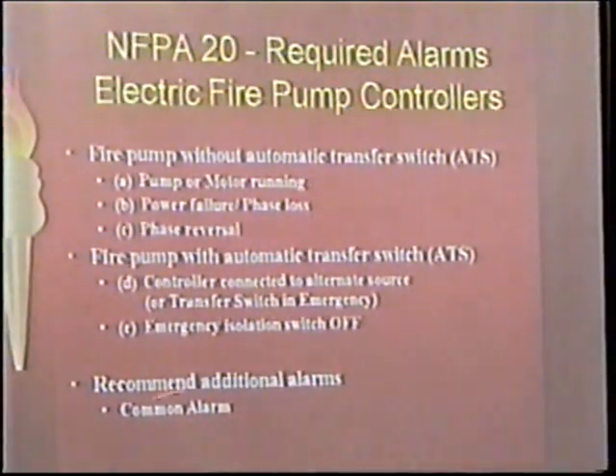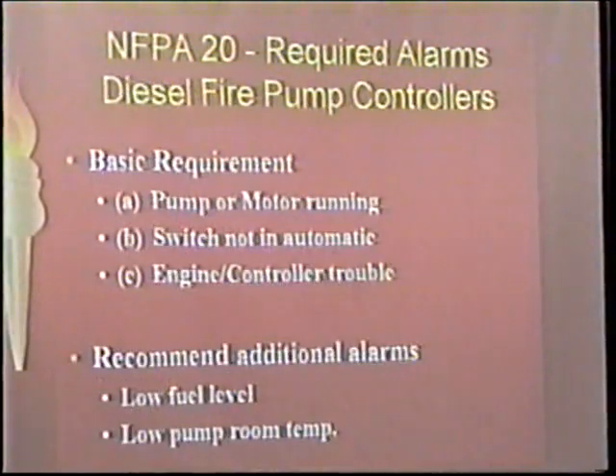And then, like I say, now with the newer computer controllers, I recommend that a common alarm be wired on all of them, because it's that common alarm that's going to pick up things that are wrong, like the memory's full, the memory battery's dying. Those alarms only come up locally, and the only way you're going to see them is if you use a common alarm output. Or you can use the new Firetrol one, which you can tie to the web and do it that way, but whatever.